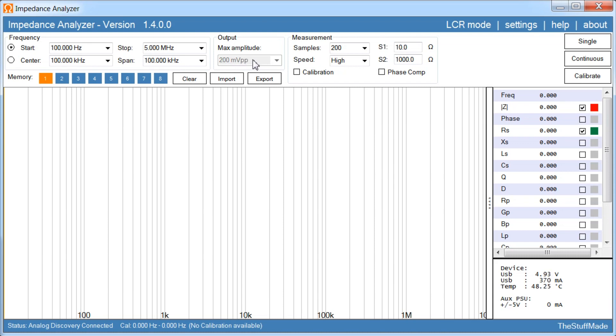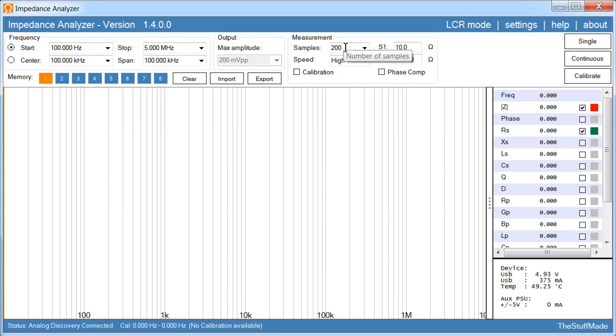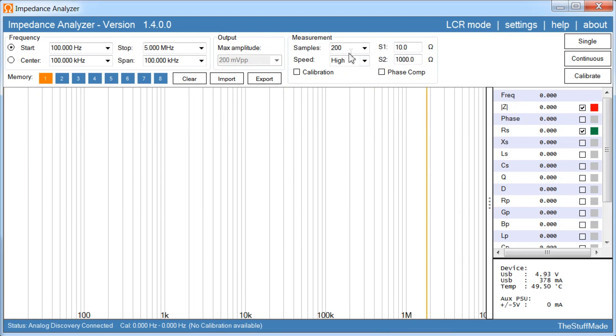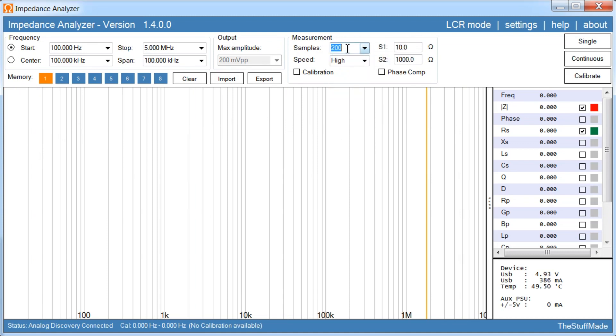What this means is whatever you are testing is never going to see more than 200mV peak to peak. And with such a low test voltage means you can also do in-circuit testing. However the actual voltage across the device depends on the impedance. Then we have number of samples across the frequency range, you can select the value here.